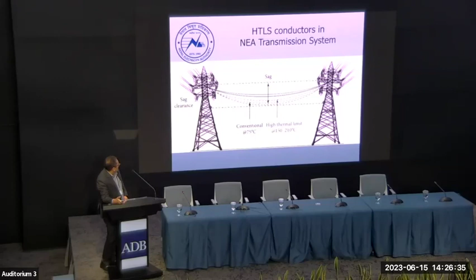So why are these called high temperature low sag conductors? The normal conventional conductor operates at 75 degrees centigrade, but HTLS conductor can take up to 150, even up to 210-220 degrees centigrade. So it can carry more current, and the sag will be less than the normal conductor. That's why it is called HTLS conductor.